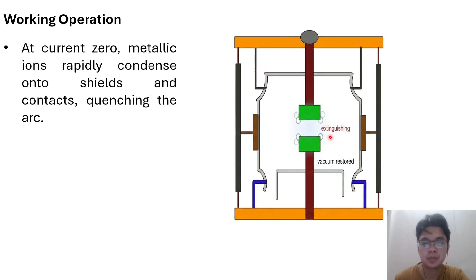So we can see here that the arc that formed earlier is now gone, or extinguished. And after the arc is extinguished, the vacuum immediately regains its high dielectric strength. So this prevents the arc from restriking or forming again between the contacts.